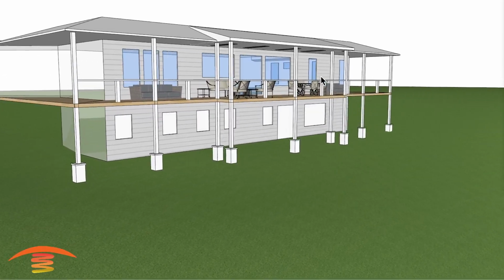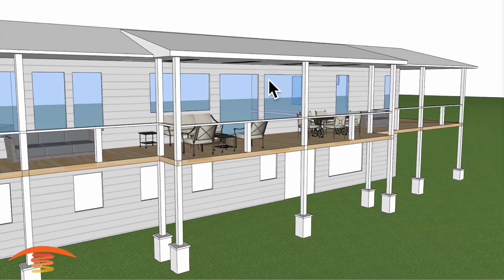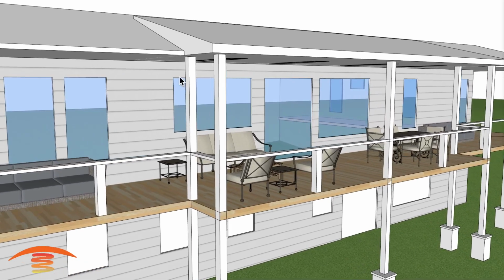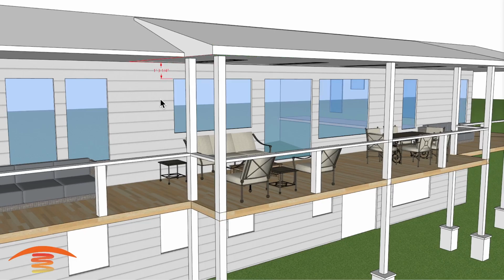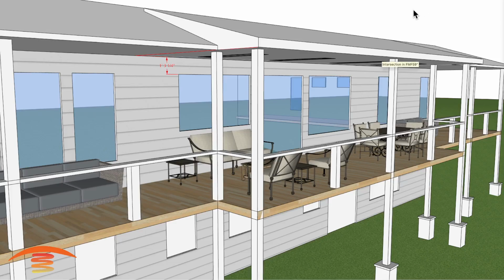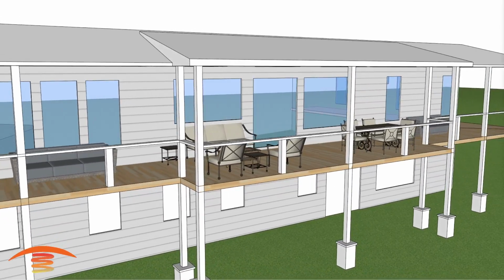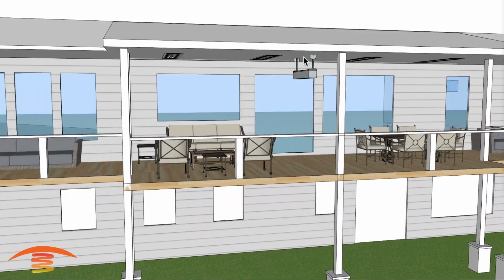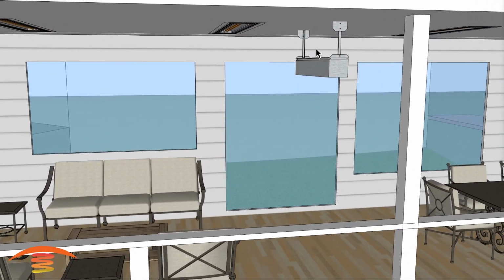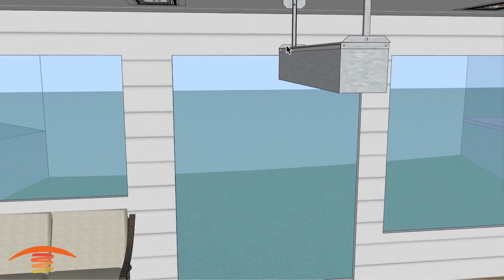The other thing that I noticed is the height of the windows here. I don't actually have the measurement here, but let's go ahead and see. I think I'm actually 3 inches off on this height, but let's just go see what I have. Yeah, so it's about 12 inches height. And if you were to place a gas heater, you need to have a clearance above the heater. So that clearance on an S34 or a TSH model is 14 inches of height, because there is exhaust that flows off of the unit itself.